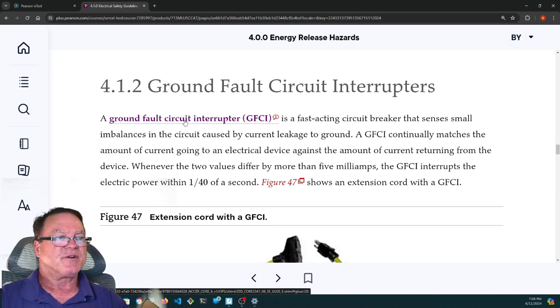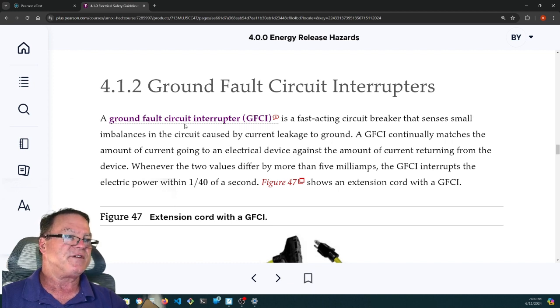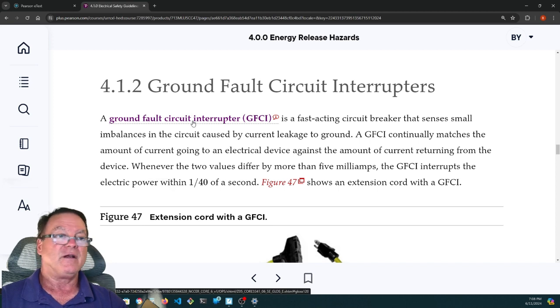A ground fault circuit interrupter is a fast-acting circuit breaker that senses small imbalances in the circuit caused by current leakage to ground. A ground fault circuit interrupter continually matches the amount of current going to an electrical device against the amount of current returning from the device. Whenever the two values differ by more than 5 milliamps, the GFCI interrupts the electric power within 1/40th of a second, about a cycle and a half.